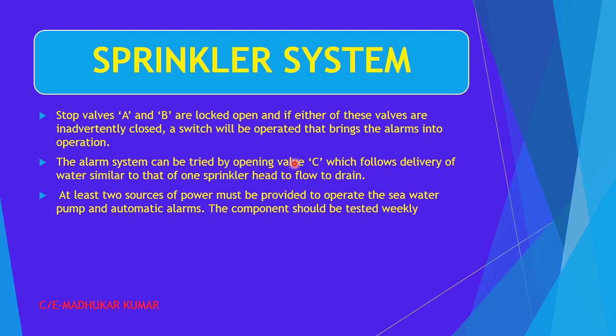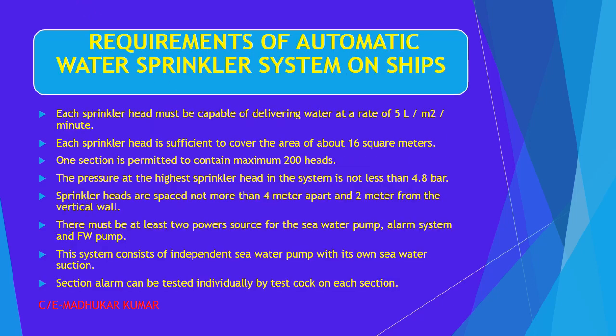At least two sources of power must be provided to operate the seawater pump and automatic alarms. So we have the main supply system, that is the main generators, and the emergency supply system also. The components of this sprinkler system are tested weekly.